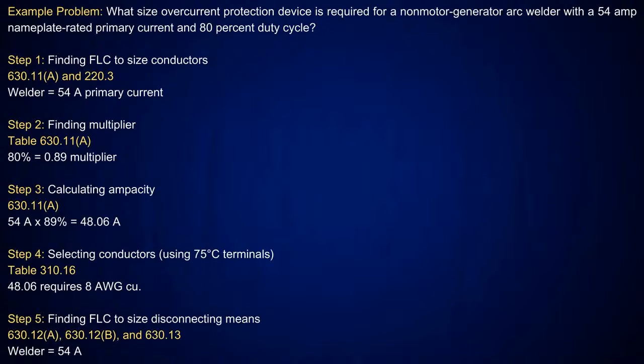So all I'm going to do is, I got a little mistake there. Oh no, that is my multiplier, 89. So I take that 80% duty cycle with a 0.89 multiplier, and it's going to tell you that it's good for 48.06 amps. Now I'm going to look at the conductors also here, because I'm doing the conductors and then I'm going to do the overcurrent device.